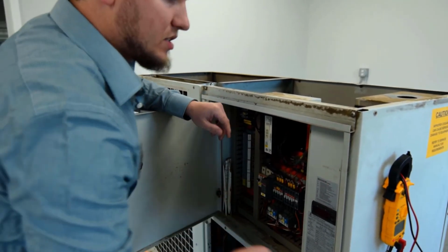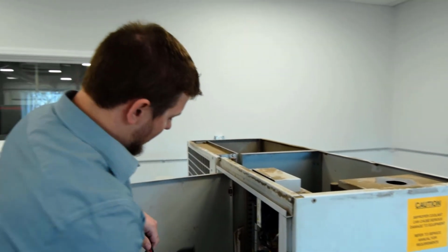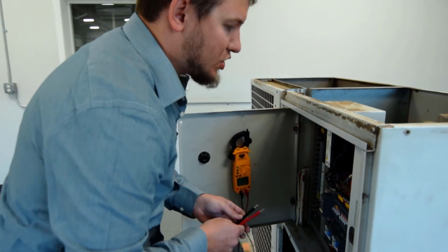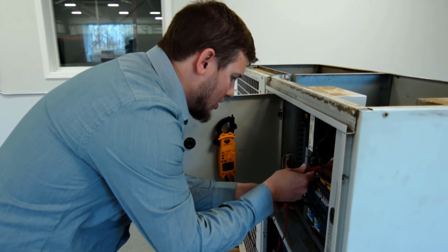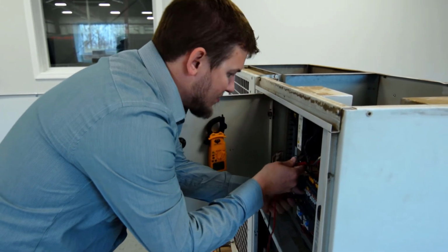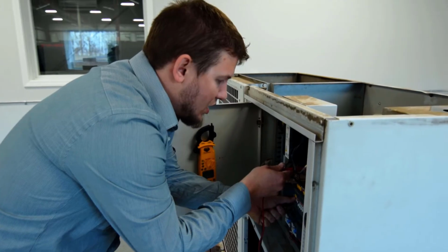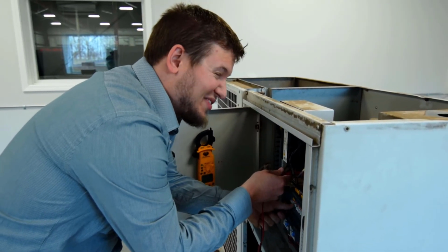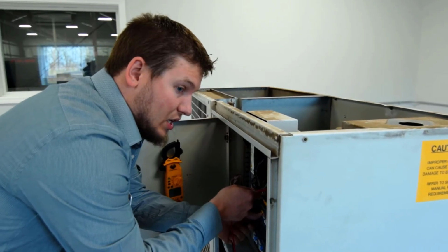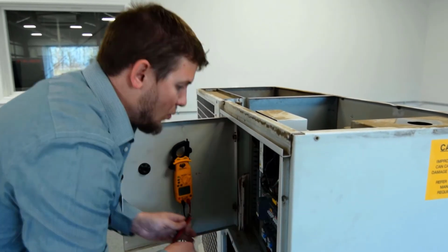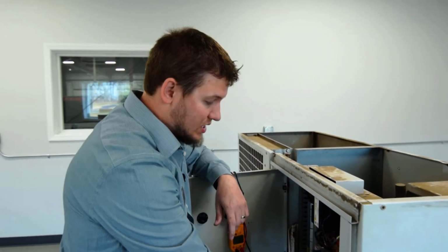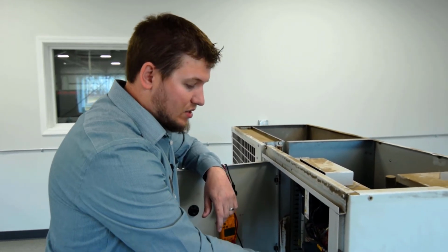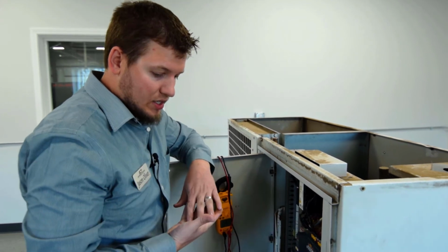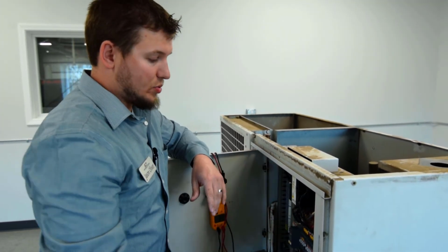Once you've verified this, the next step is to take your multimeter and do a resistance check from the outlet of the contactor or the main breaker through the outlet of the contactor. The best way to do this is to push in the contactor to get a resistance. If you're getting a resistance greater than like a 0.2 to 0.5, please contact ACT immediately to help us so we can help you troubleshoot it. Once you've done all this, verifying that there's less than 0.2, you can go ahead and move on to the next step. Step number 6 on this checklist is to verify that there's no voltage drop between the contactors.